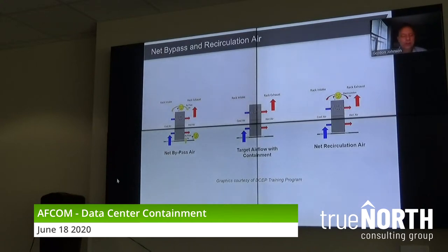I want cold air to come up from the perf tile, down from the overhead ductwork or from the inlet cooler. And I only want it to do one thing. I want it to go into the inlet of your server. And out of your server exhaust, I don't want that air coming back into the inlets or going anywhere except directly back to the cooling unit. That's it. That's once through cooling.